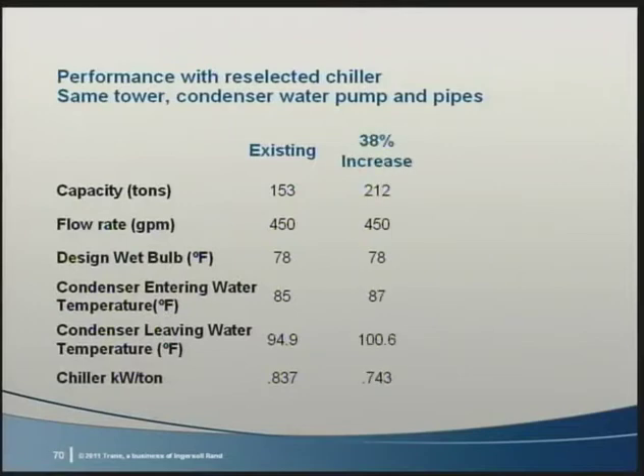The chiller needs to be replaced, but the building requires more capacity. So we want to increase the capacity when we purchase a new chiller, but use the same condenser water pump, pipes, and cooling tower. If we reselect the tower at different conditions, we find that it can easily reject the additional heat from a higher capacity chiller. Combining tower and chiller selections, we can see that we can select a chiller that can either produce 38% more tonnage, or we could select an even larger chiller that would give us up to 51% capacity increase.